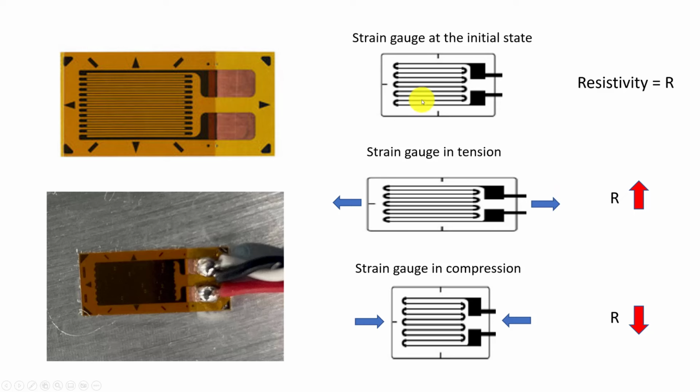So we install these strain gauges in the initial state where we don't have a load on there. We're going to glue it to an object. We'll have a video that talks about how to do that correctly and attach wires to it. That's going to have some resistance value, just like a resistor. As we stretch this, we're going to stretch it by these alignment marks right here. You see these two little ticks right here?